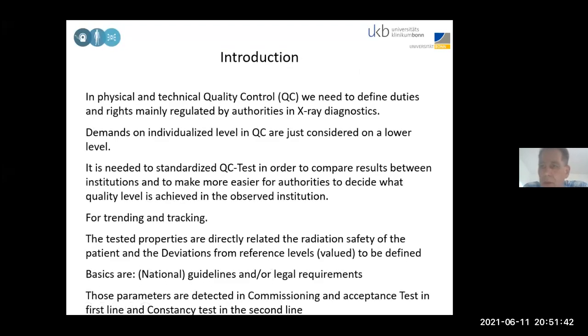I would like to give you a short introduction about the quality control itself, so why it's important that we have quality control in radio diagnostics. The quality control is actually demanded by our authorities. So it's mainly regulated on a legal basis. You have guidelines, and it depends on the country which guidelines you have to follow, but there are guidelines. If there are no guidelines, the guidelines are given by the vendor itself. So if the machine is going to be installed, commissioned or accepted, then the vendor has at least a bunch of parameters and properties which need to be tested.